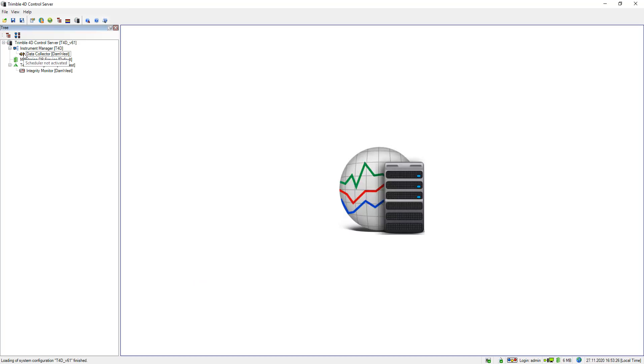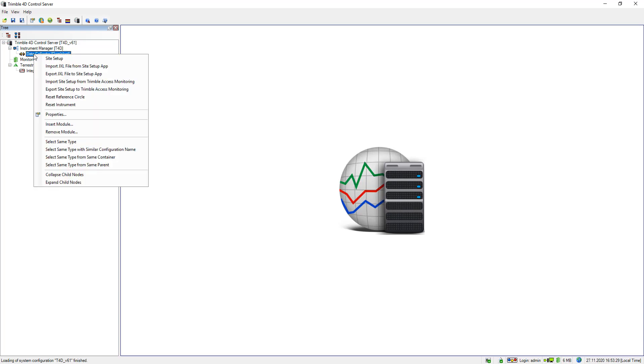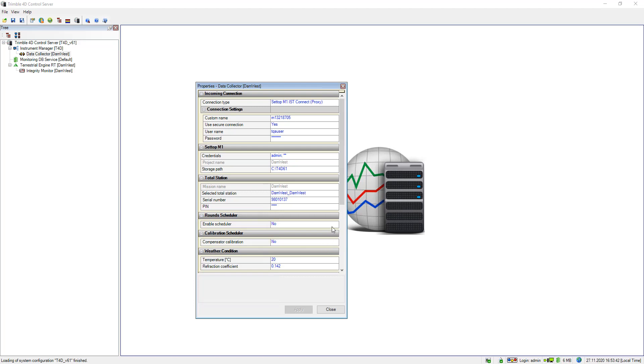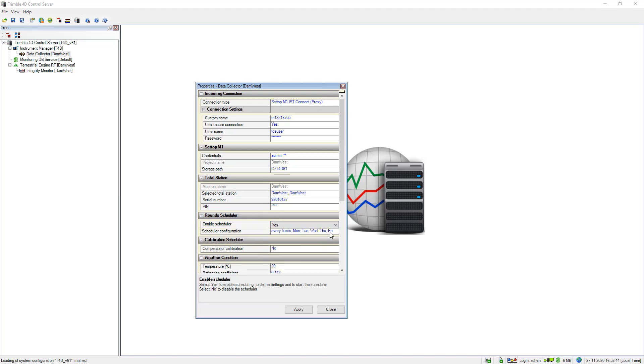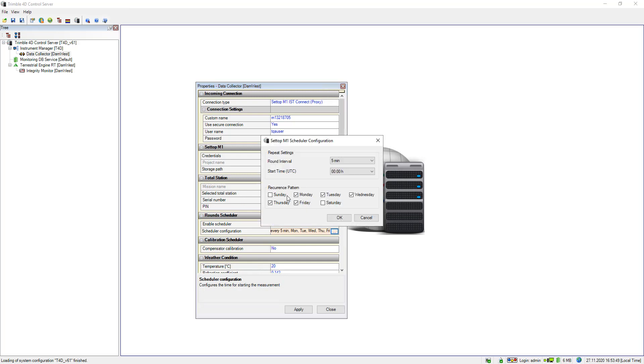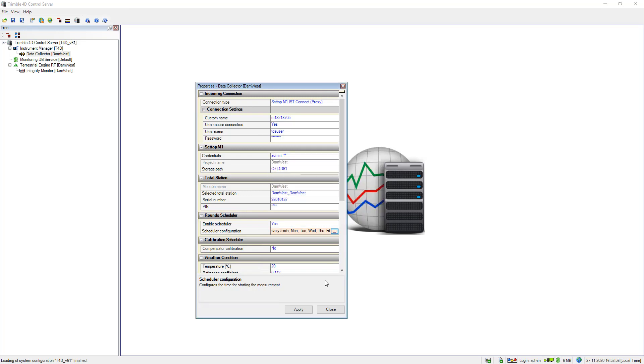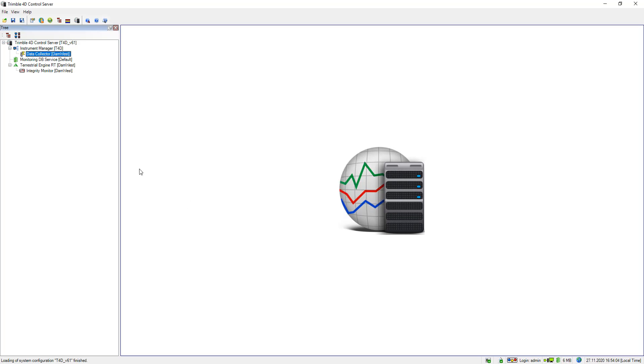When I now hover over the data collector module it says the scheduler is not activated yet, so I do a right click, go to properties and here I can enable the scheduler. I say yes and another window opens up. Here you can specify your recurrence pattern. For example I don't want to measure on Sunday and on Saturday, so on the weekend. Round interval is set to five minutes and I click on apply. So also this is applied to the setup M1 and now the message says waiting for next round.